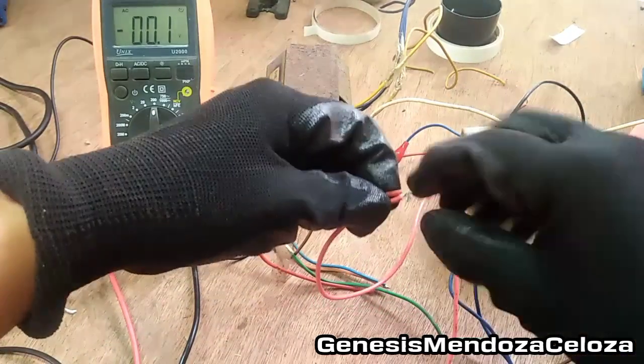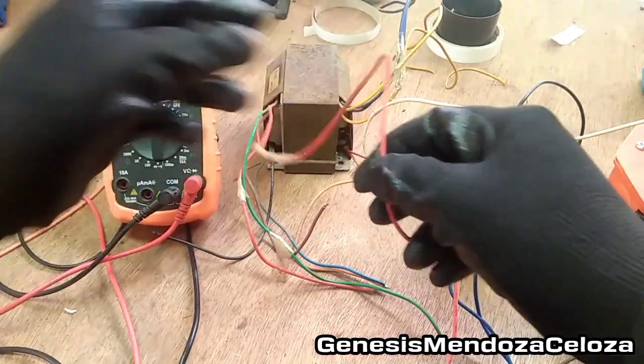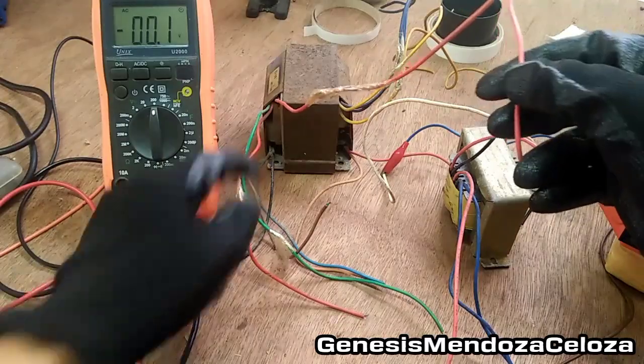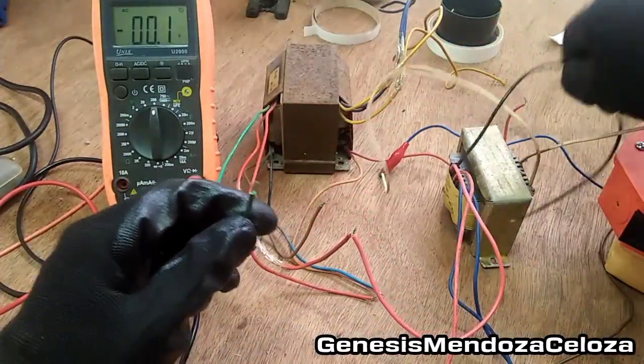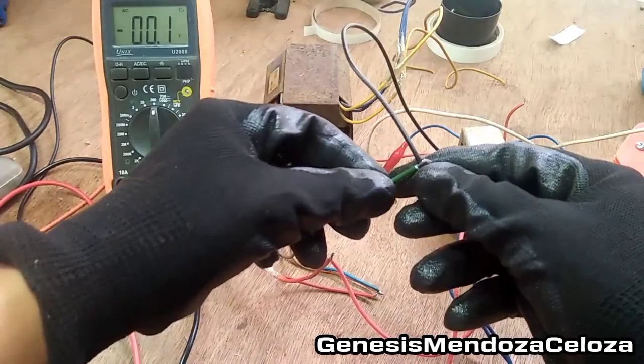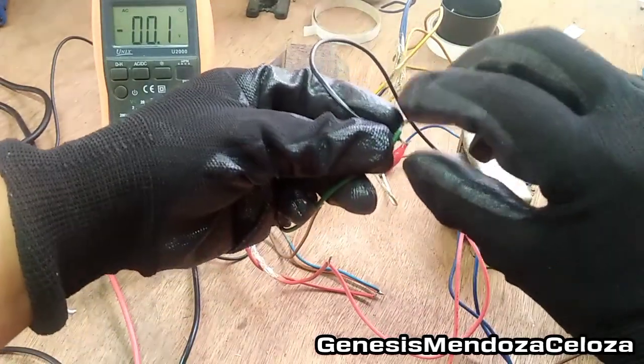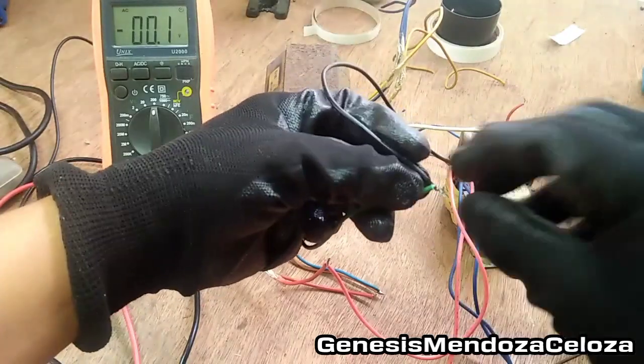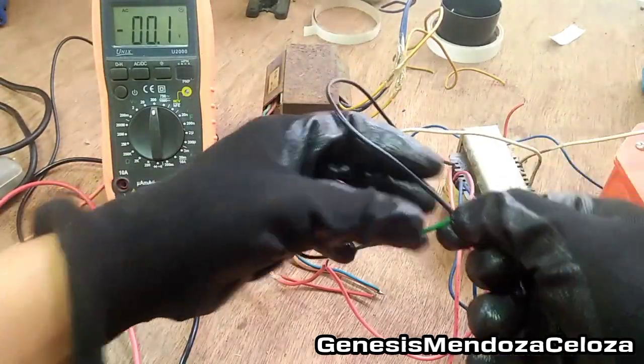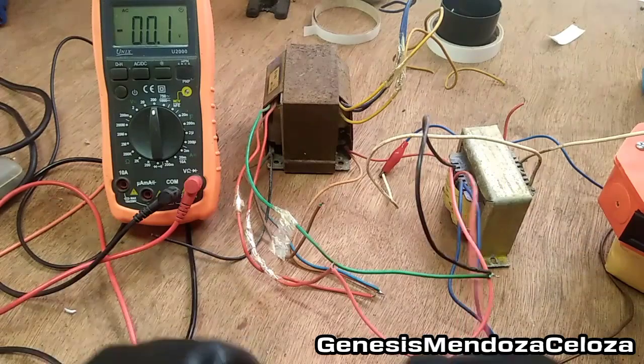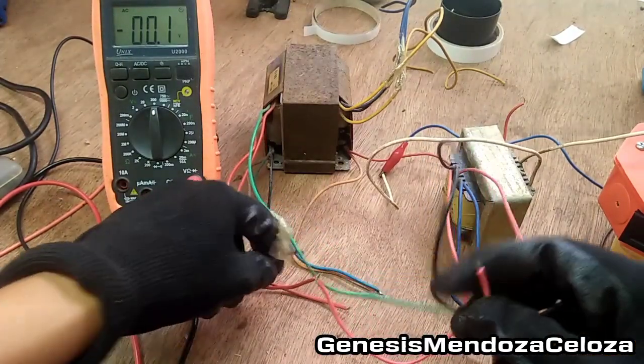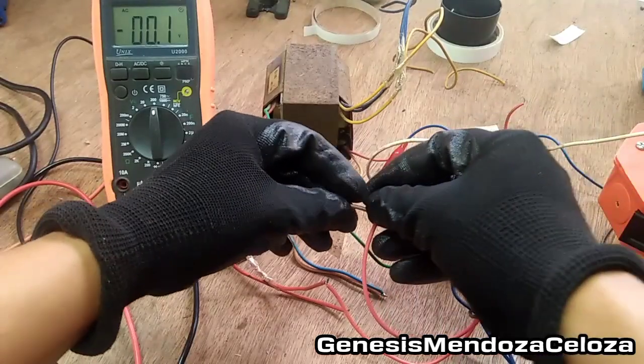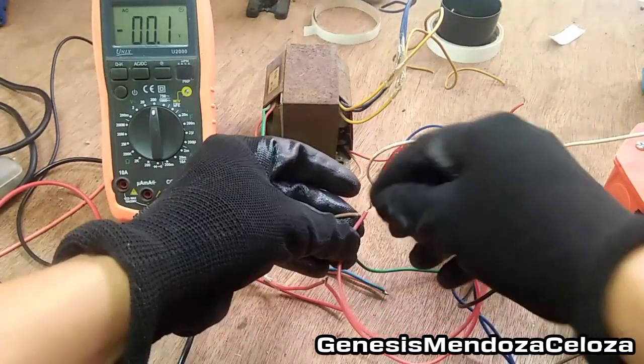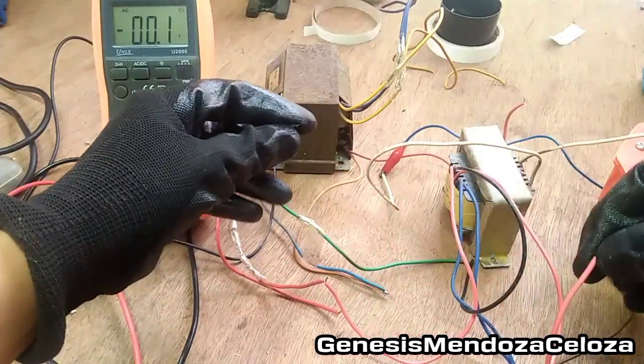An isolation transformer, as its name implies, provides a barrier such that accidental contact with an earth ground results in negligible current flow, only due to parasitic capacitance and inductance of the transformer. A slight tingle at worst. This also protects your test equipment, as well as the device you are troubleshooting, since a similar accidental contact can result in a short circuit, sparks, smoke, and many destroyed parts.